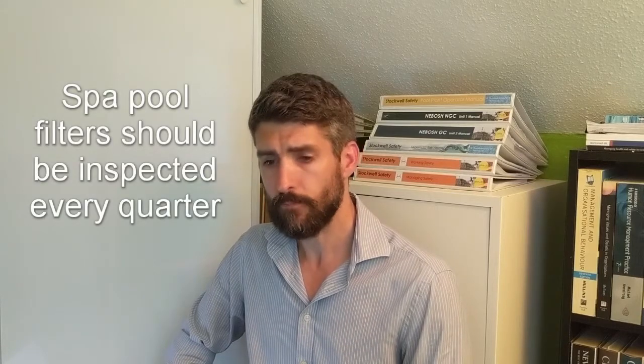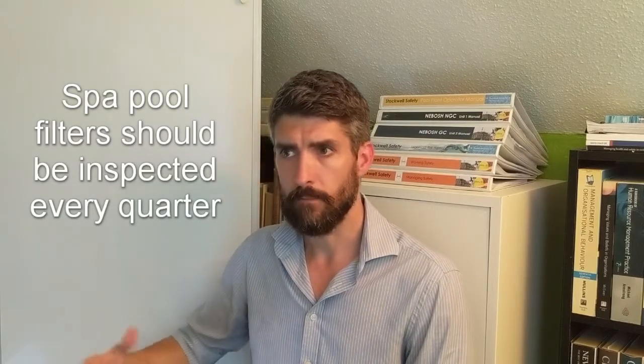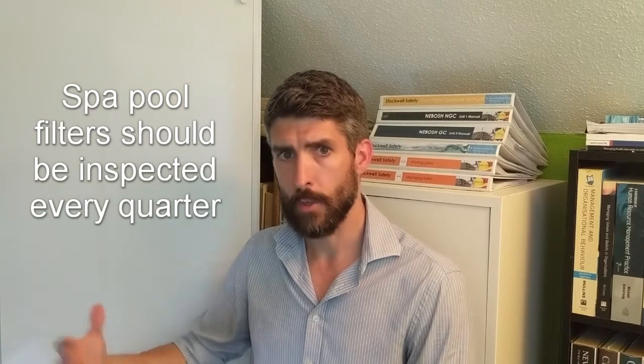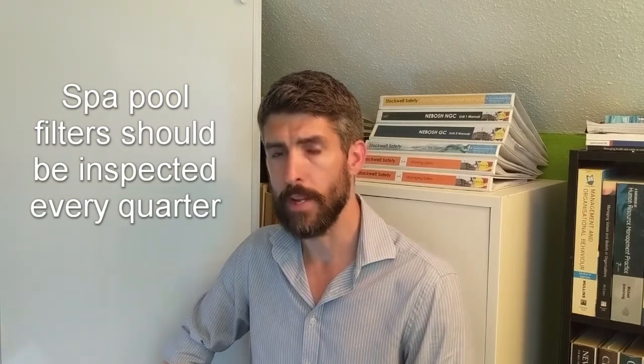So cleaning is essential, and as I said, backwashing should be done every single day. On top of that, the filter itself should be maintained on a much more frequent basis than a typical swimming pool filter would. At least once a quarter it should be inspected.